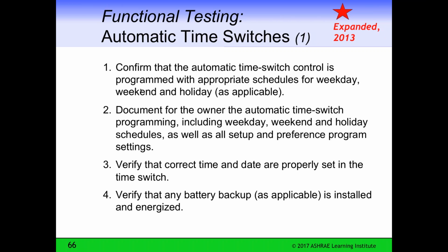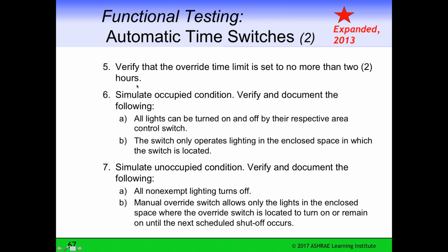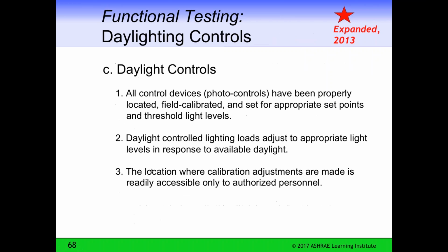For automatic time switches, you have to confirm that the automatic time switch control is programmed accordingly for weekday, weekend, and holiday. You have to document for the owner that the programming is well set up, and you have to verify that the correct time and date are properly set in the time switch and that any backup is installed. There's more on time switches, but I won't go into that detail.